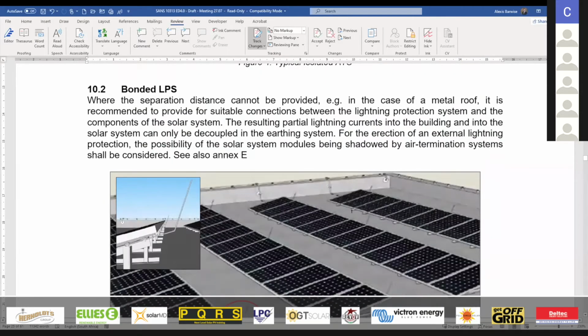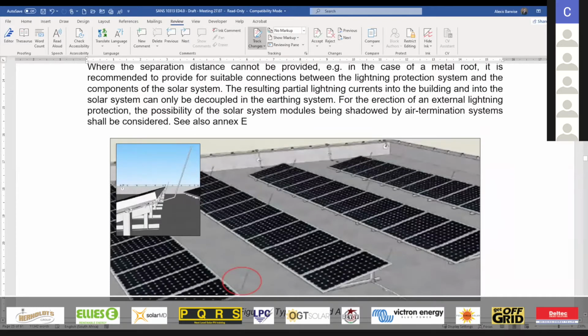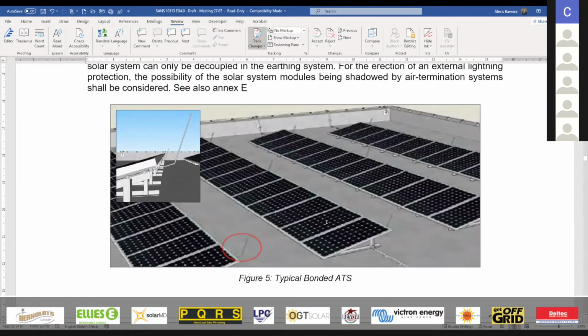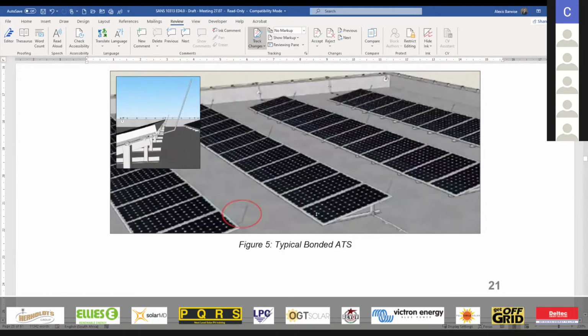When we look at a bonded system, that is when we have a physical connection. You can see here a physical air termination rod. Bonded systems are predominantly on IBR sheeted roofs. We see them so much these days, where you cannot physically separate the lightning protection system from the PV system. It's all bonded together. This is still acceptable, nothing wrong with that. The only difference is now we will have to bond with higher or bigger sized cables in order to carry obviously the bigger lightning currents.